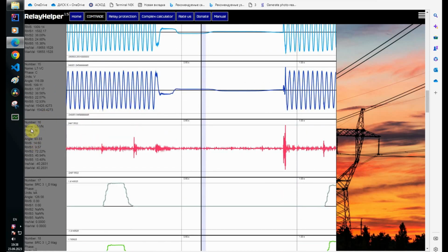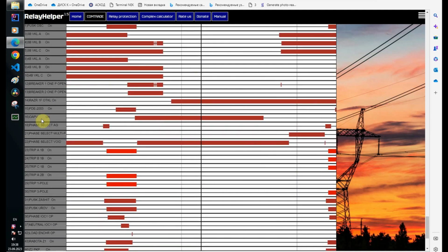We had a one-phase trip, then a three-phase trip occurred. This was a malfunction, but L60 is not the reason. In this case, the device worked only with backup protections. This is the first zone of distance protection work. And here is the short-term operation of the load encroachment.